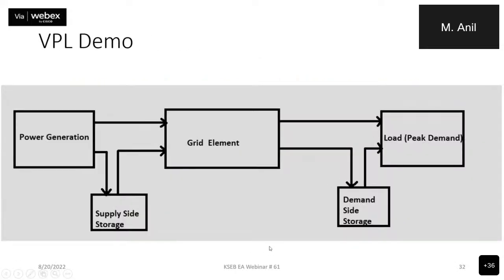So a VPL demo is shown in the picture. So power generation, at the point of generation, we have a supply side storage. And at the point of load, that's the extreme right, we have a demand side storage battery. So we have a supply side battery energy storage system and a demand side battery energy storage system. Grid element is typically a transmission line or a sub-transmission line based upon the voltage levels.